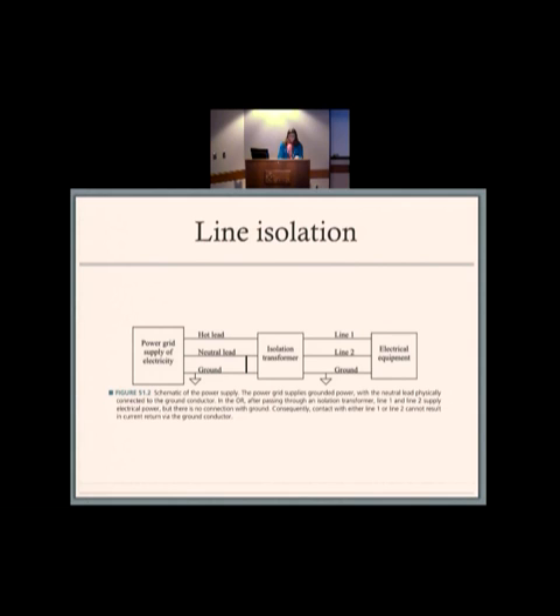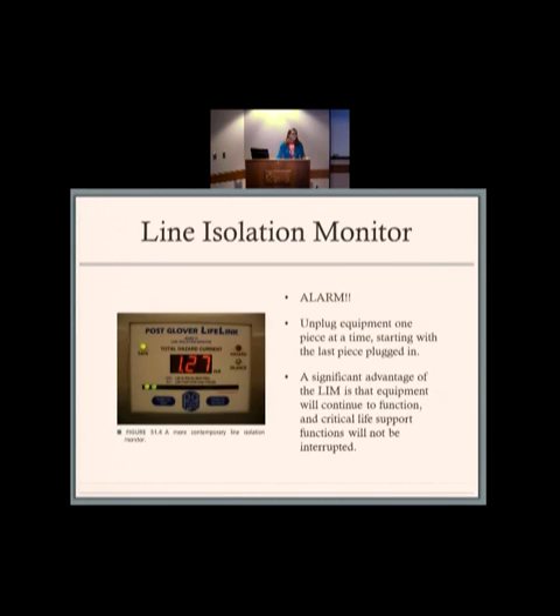So if the line isolation monitor goes off, you're supposed to look around and see what piece of equipment is faulty - take one piece out at a time. If the big monitor for the whole line goes off, that's the broken piece. If not, you plug it back in and try the next one until you find the broken one. I wouldn't get too bogged down in exactly how it works, because it is confusing, but the idea is you won't get a shock from small amounts of leakage.